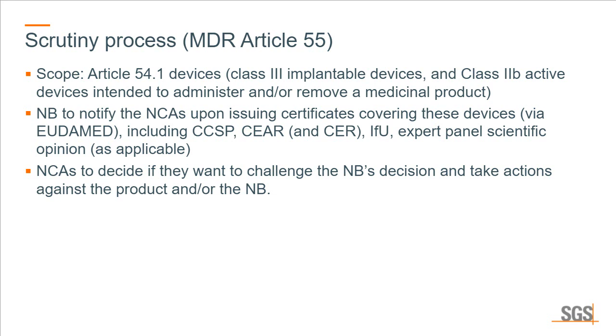And we need to include certain information, like the SSCP, CER, that's our clinical evaluation report, the original clinical evaluation report, IFU, expert panel, scientific opinion as applicable. And based on this, the competent authorities are going to review this, and they will decide whether we were right to issue a certificate for the device or they can challenge this.